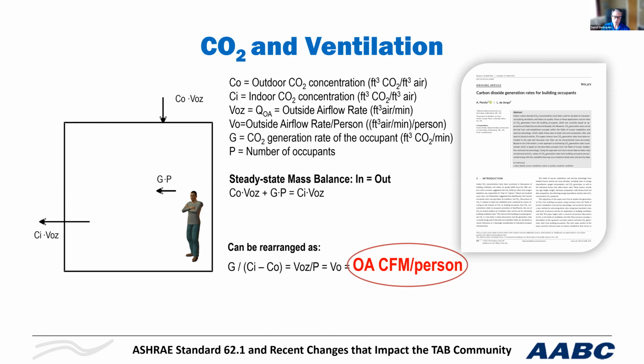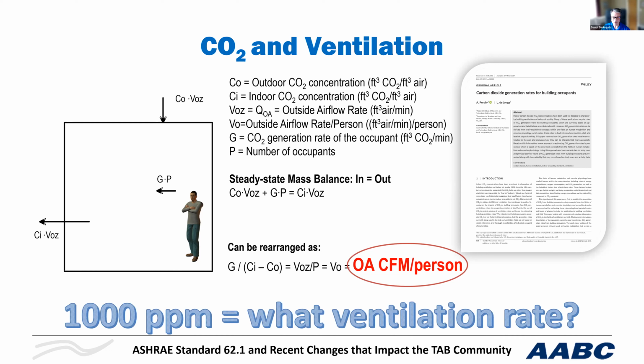So there's a direct correlation between CO2 level and ventilation. They're interdependent. If you know the generation rate and you know the CO2 value, you can estimate the ventilation rate per person. That's why CO2 is used, because each person generates a similar amount, but it is different. So this is an estimate, and it's certainly not a direct measurement of airflow. And here's the magic number. Not all spaces are 1,000 parts per million, but this is what I see on many design documents.